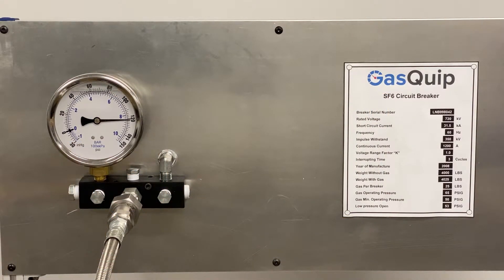Next, check to see if you have adequate gas pressure coming from the breaker. Most testers require more than 7.5 psi, which is about half a bar, and generally less than about 150 psi.